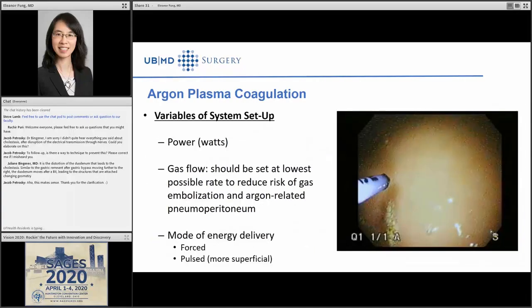In terms of the setup, you can set it up based on different power wattages. You want to have a low gas flow to reduce the risk of gas embolization or causing pneumoperitoneum. In terms of the mode of energy delivery, forced energy delivery is more continuous and causes deeper penetration, compared to pulsed energy delivery, which is more superficial and intermittent.